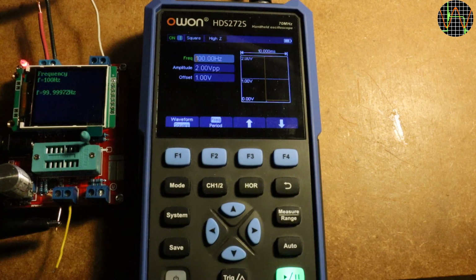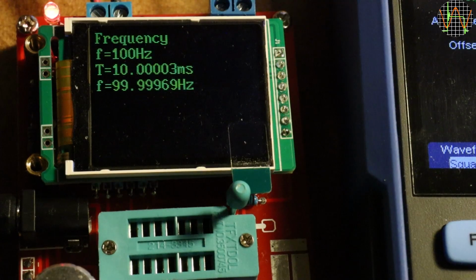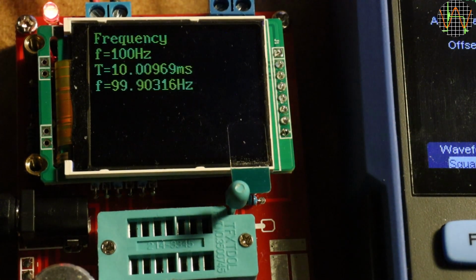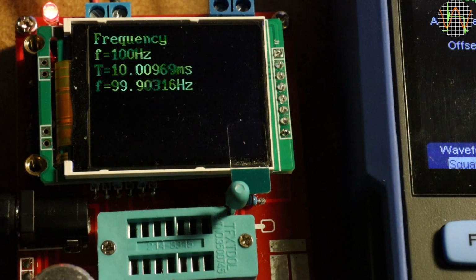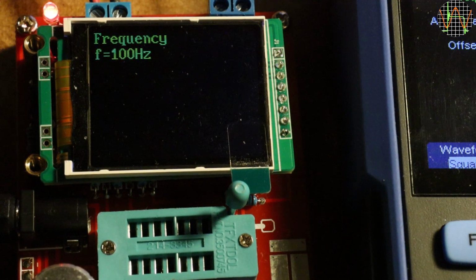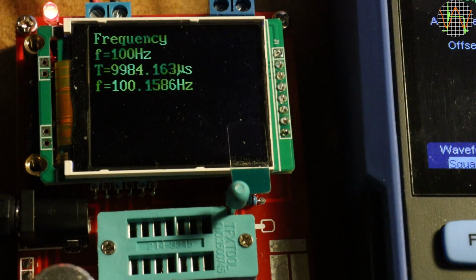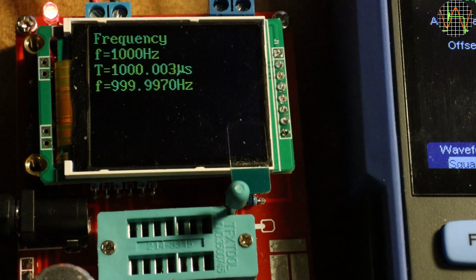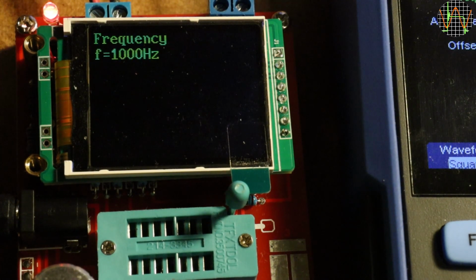How accurate these measurements are depends, of course, a little on the calibration and drift of the 8 MHz crystal in the tester. In fact, up to the frequency of 25 kHz, the tester first measures the frequency and then measures separately the period, that is the second line, and converts that to frequency, which is the third line. Same method, but now 1000 Hz and no problem here.